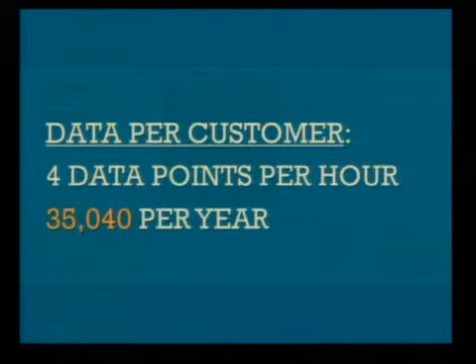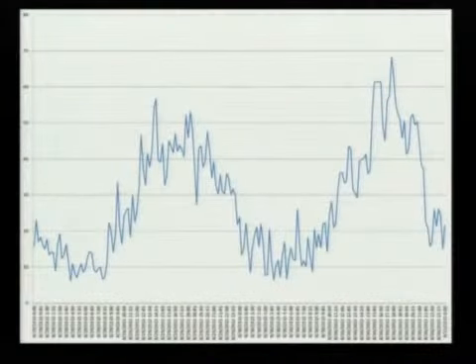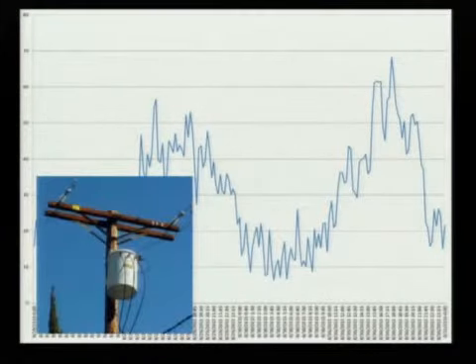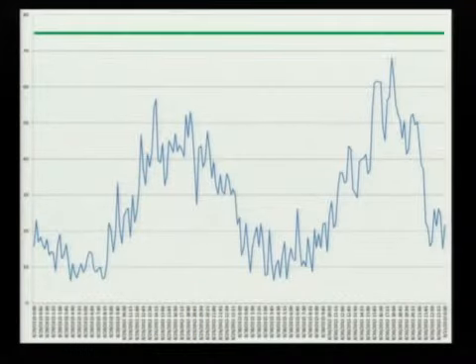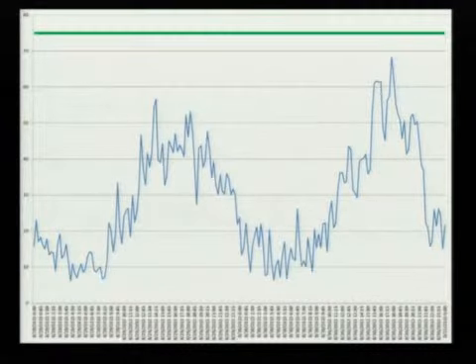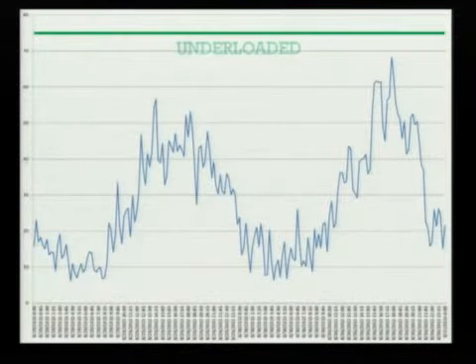But with all that data, we can do some pretty interesting things. One, for the first time, we could actually see what our load on our transformer looks like. And I mentioned before we had the two main problems, an underloaded transformer or an overloaded one. Well, now visually we can make that determination. So let's say that green line up there represents your capacity on your transformer. Well, since that graph never really touches that, I would say it's probably an underloaded transformer.